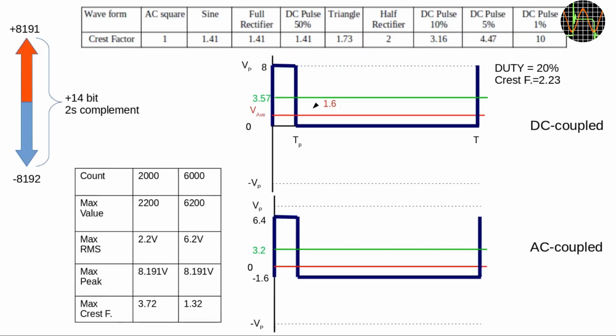The problem is that complex waveforms with a high crest factor can have significant peak values but a comparatively low RMS. In today's electronics, pulses are far more common than pure sine waves, and being able to handle a sizable crest factor and still showing the correct RMS value is important. In the UT210E, as in many other meters, there is some signal protection and clamping, but then everything is done inside the chip. There isn't a traditional range switch or AC coupling capacitor to block DC in the AC ranges.